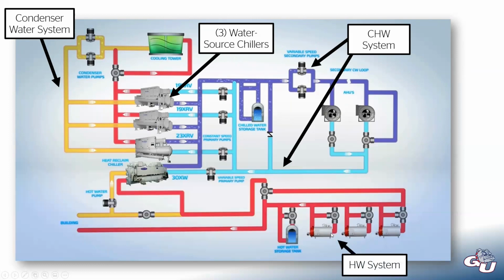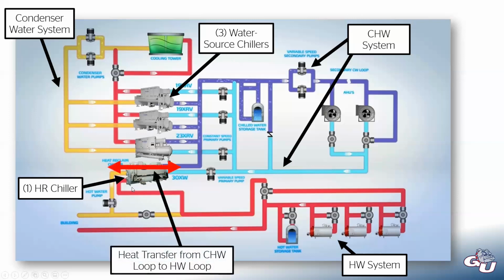And then down here, we have our hot water system. So a bunch of boilers producing hot water. And then we have this 4th chiller right here, which is our heat recovery chiller. And you can see that this chiller has on one side of it chilled water in and out, and on the other side it has hot water in and out. And so this is actually going to transfer heat from the chilled water side into the hot water loop. So instead of rejecting it all at this cooling tower up here, let's take some of that and dump it into the hot water stream. And that way these boilers don't have to work quite as hard.